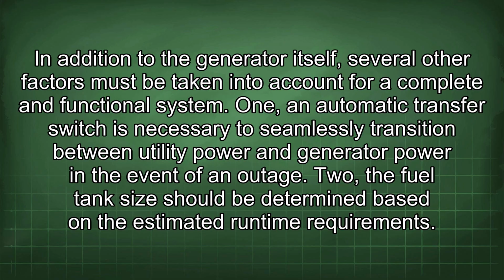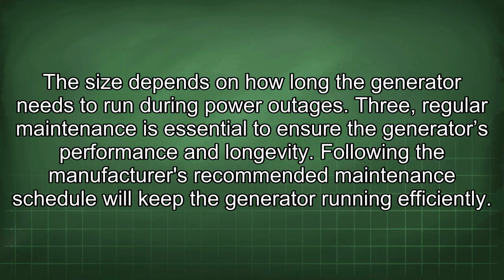In addition to the generator itself, several other factors must be taken into account for a complete and functional system. 1. An automatic transfer switch is necessary to seamlessly transition between utility power and generator power in the event of an outage. 2. The fuel tank size should be determined based on the estimated runtime requirements. The size depends on how long the generator needs to run during power outages.